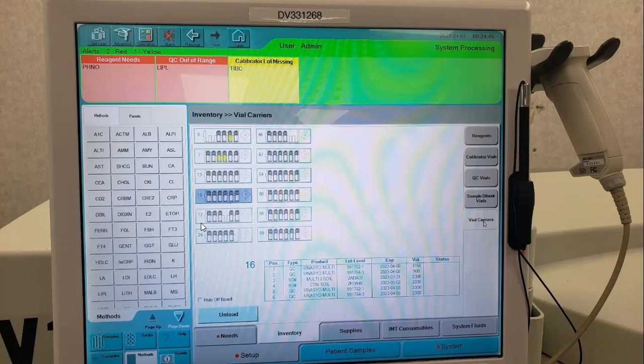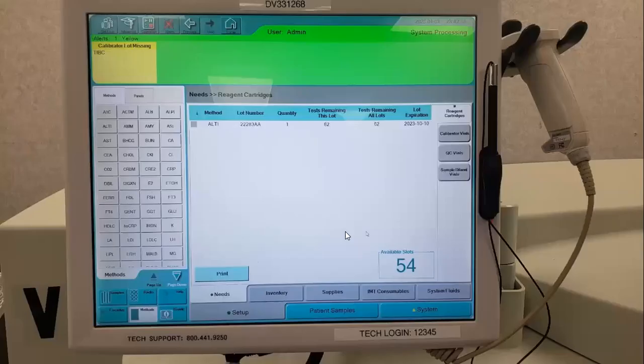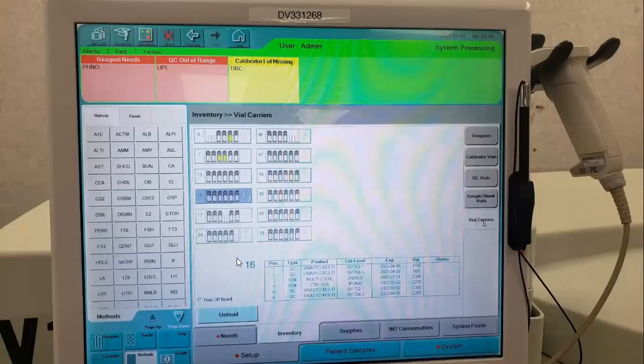Numbers between 1 and 20 we keep just for our QC material, so they line up first, so we can know exactly where to go when we're running QC. Calibrators run on anything 20 and above, just for the vial carriers. This little 16 that we have down here is because we have selected vial carrier 16, and it will show you what type of material is on it.